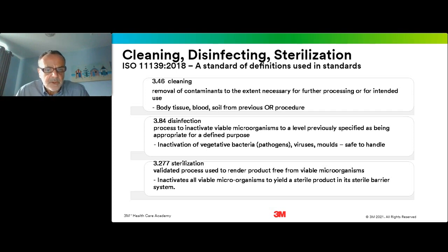Disinfection does not, of course, inactivate the more resistant microorganisms such as spores. And this is the purpose of sterilization, which is a validated process used to render product free from viable microorganisms, all viable microorganisms. So when we've done our sterilization process in the sterile barrier system that we're going to use, the packaging, then we will end up with a sterile product that's ready for use in the next surgical procedure.